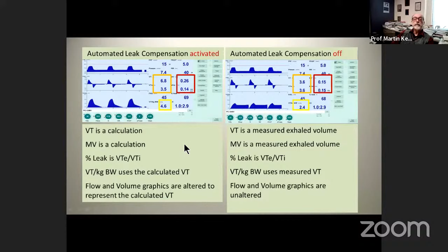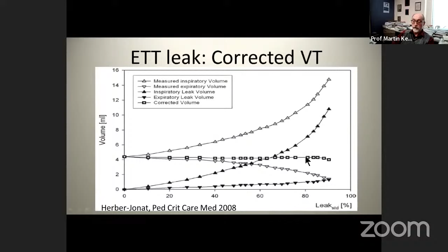And these are some data where they looked at progressively larger leak around the endotracheal tube. Volume is on the vertical axis here, and you can see that the tidal volume with no leak was a little over 4 per kilo, 4.5 per kilo. But as leak progressively increased, the measured inspiratory tidal volume deviates progressively more. They used relatively low PEEP, so the exhaled tidal volume was not as much affected, but the calculated tidal volume remains remarkably stable, up to leaks of almost 80% or so. So the leak compensation is a really cool feature and should always be used from my perspective.